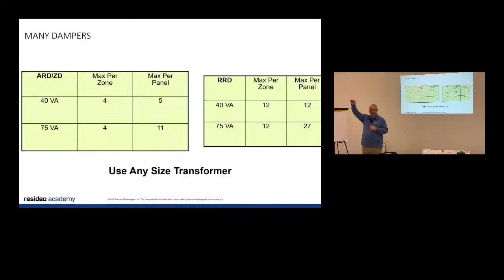So you tie up all the upstairs ones together, all the downstairs ones together, and you bring that back to the panel. So when my thermostat in the basement calls, I get all 6 open for the basement. I close everything upstairs, I get satisfied, I close everything, and then upstairs calls, downstairs shut, and then I'm just trying to deflect the air or distribute it in the right direction. Clear? And you can do that.